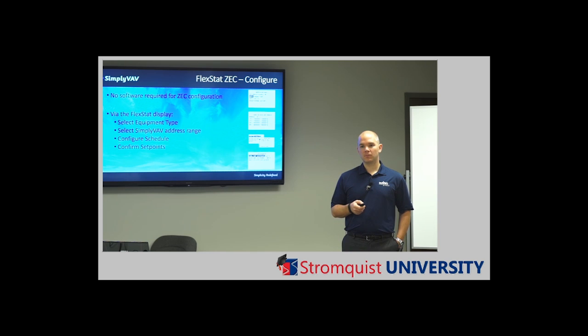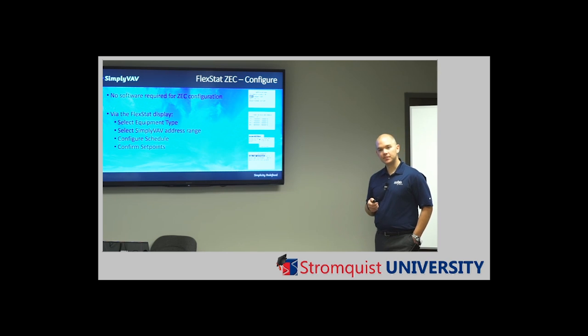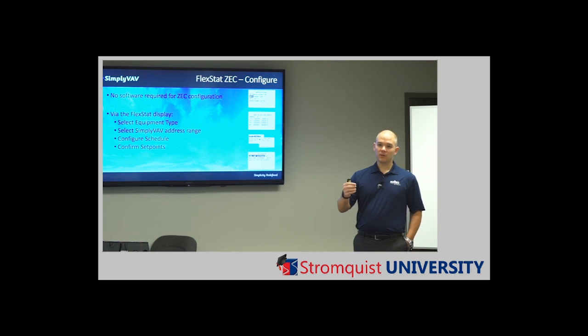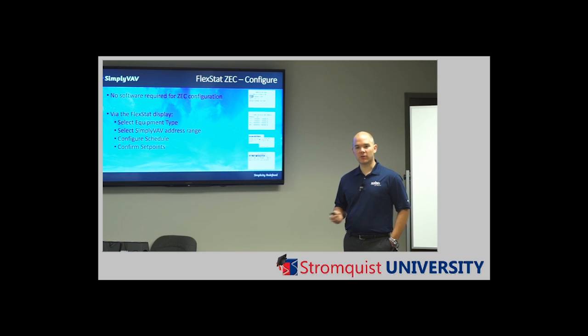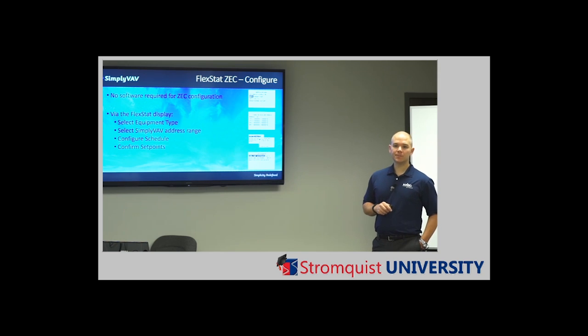You do that via a BACnet interface, or is it actually programming software? That would be with a software utility from KMC. Like BACstage or something? Yep. Those programmings are just like a regular FlexStat. They're exposed, but they're not editable. So you'd shut off the factory program, turn on the open program and do your custom programming there. And then you can use the staging program that we already have there to control the equipment. So that's something we could do for a customer if they wanted something special. We could do it here, then send it out, and...